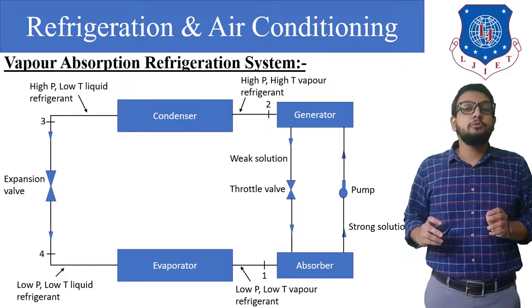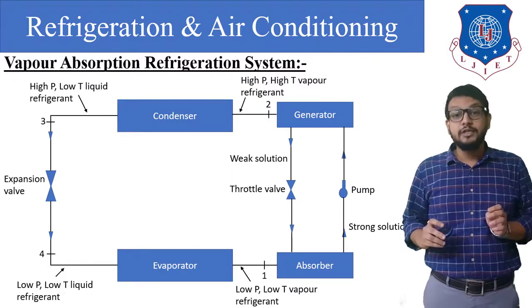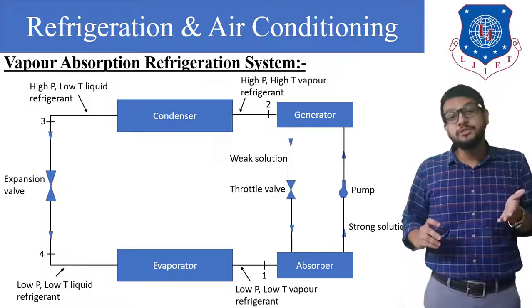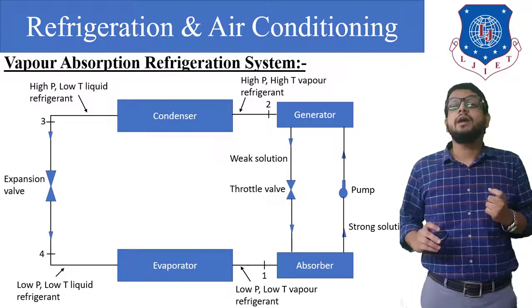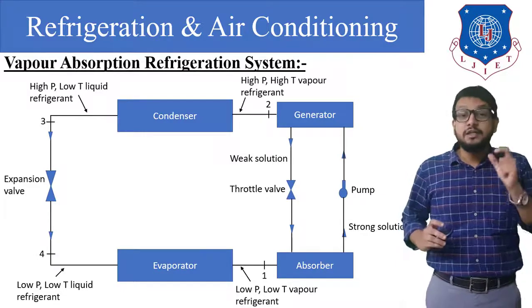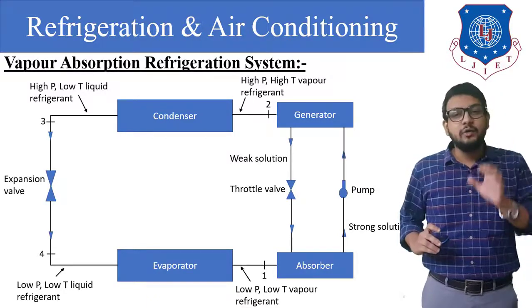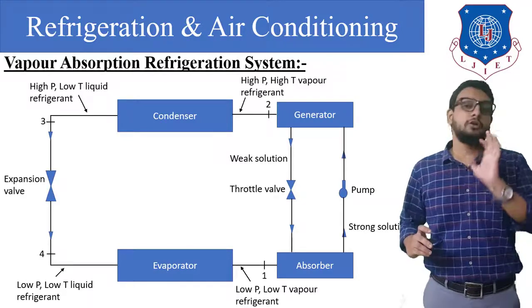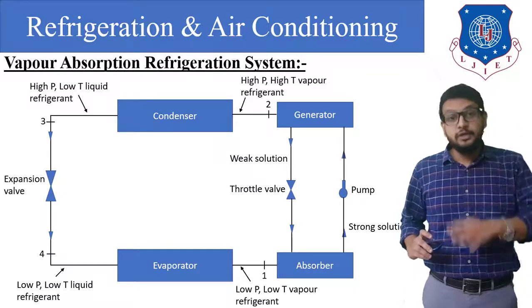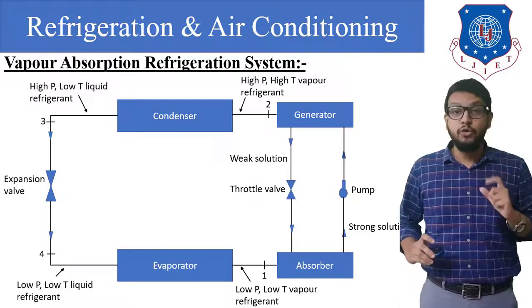As the name itself suggests, vapor absorption means vapor will be absorbed. The refrigerant used is ammonia (NH3). Ammonia has a very important characteristic: it can easily dissolve in low temperature, low pressure water — that is, ammonia has high solubility in cold water. As temperature increases, the solubility of ammonia is reduced. Because of this property, ammonia vapor is absorbed.